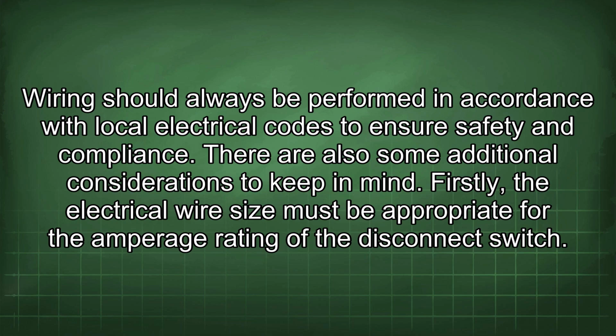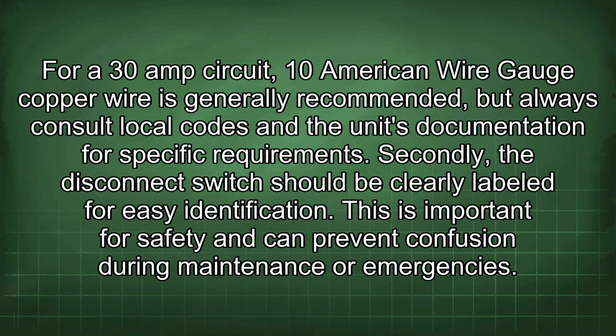There are also some additional considerations to keep in mind. Firstly, the electrical wire size must be appropriate for the amperage rating of the disconnect switch. For a 30 amp circuit, 10 American wire gauge copper wire is generally recommended, but always consult local codes and the unit's documentation for specific requirements. Secondly, the disconnect switch should be clearly labeled for easy identification. This is important for safety and can prevent confusion during maintenance or emergencies.